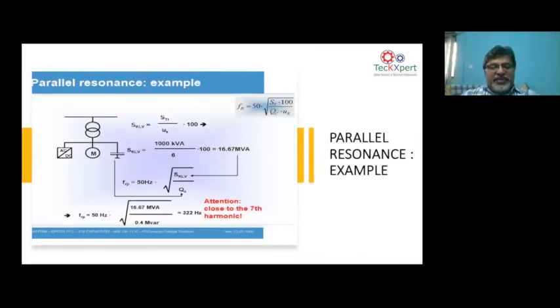So now this is again showing if you put a simple capacitor. I mean, again, it's a very important slide, because normally when you put a capacitor bank to a transformer, here it is showing a 1000 kVA transformer, and you're putting a 400 kVAr, 0.4 MVAr, that is 400 kVAr capacitor. When you put a 400 kVAr capacitor to a 1000 kVA transformer, you will have a resonant frequency at 322 Hertz. That means, if you have a variable frequency drive installed in the plant, or if you have any other power electronics which is producing 5th or 7th harmonic current, you can have a parallel resonance taking place because of a capacitor sitting in the network, which is 400 kVAr vis-a-vis a 1000 kVA transformer.